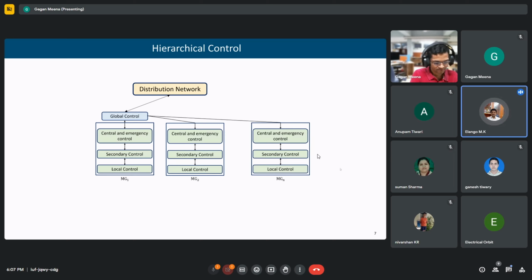Based on the formula for calculating time setting multiplier, it's based on two currents, positive sequence current and negative sequence current. Actually, last week too, I tried to discuss the same question. Based on the formula, two currents are considered to calculate the time settings, but the option is only positive sequence or negative sequence or some other. And the answer they gave is negative sequence component current.